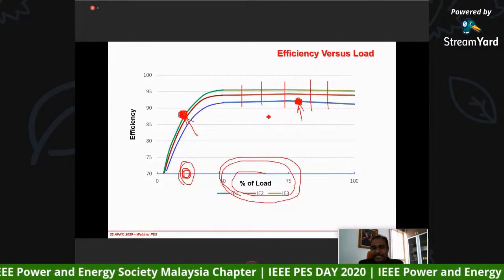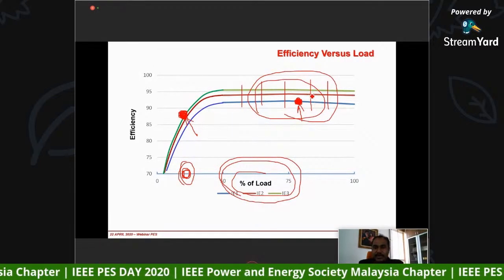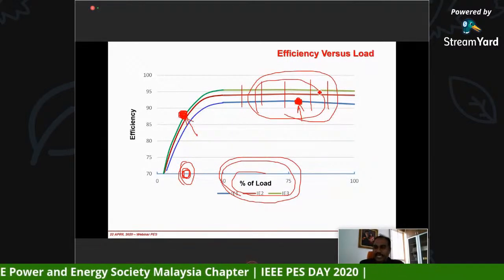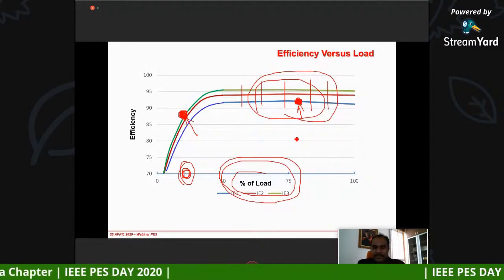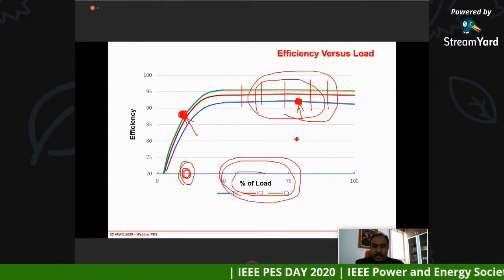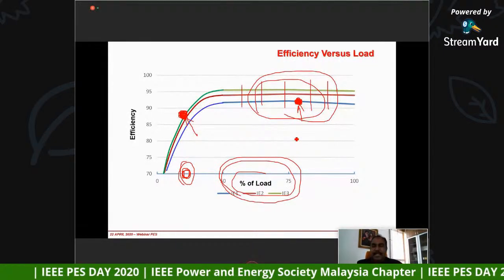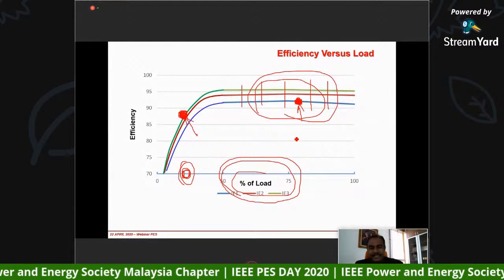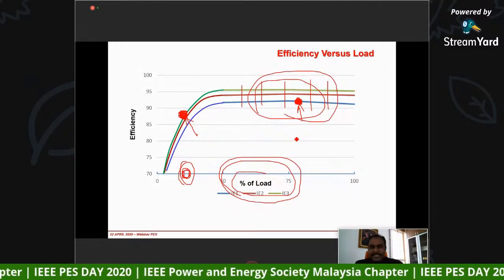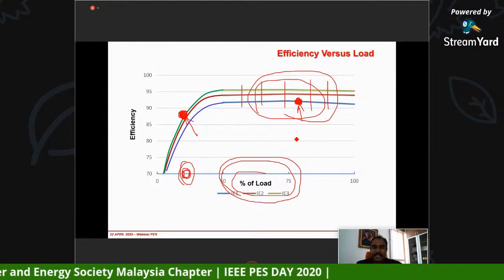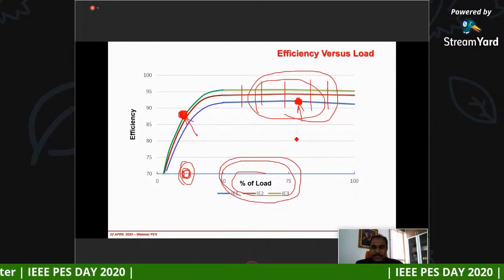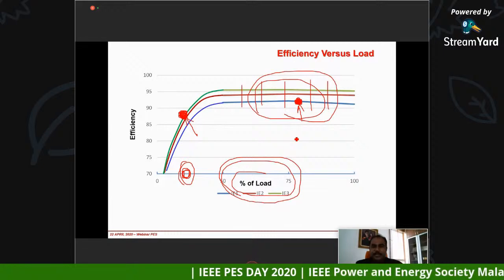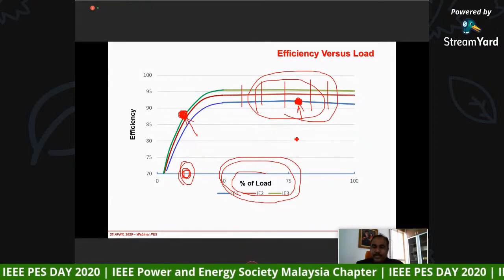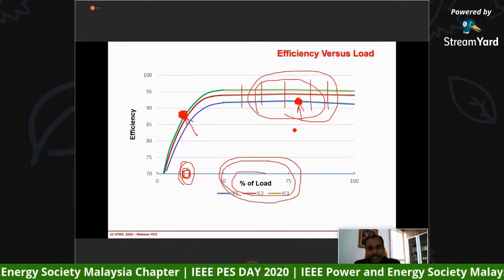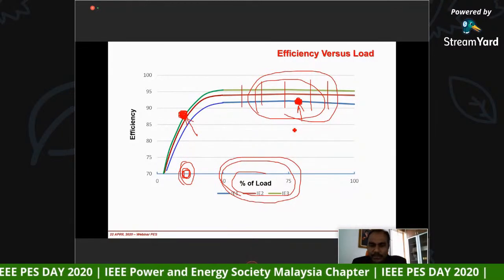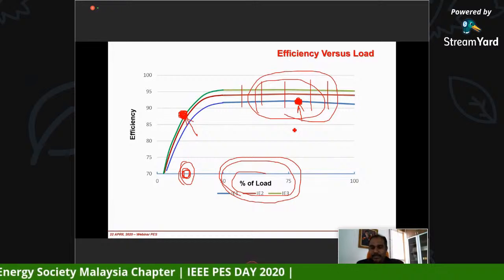If you're operating at this region, of course you can see that by going for IE2 or IE3, you'll be able to see the savings, right? But we have seen many cases in industry where the loading is like 50%, 40%. In that kind of system, when you're upgrading with the same power value of the motor, you will notice that you're not going to see any savings. So that is the big mistake. What you have to do is resize the motor so that the motor will be operating at higher loading condition, and then you think about going for higher efficient motors, right?